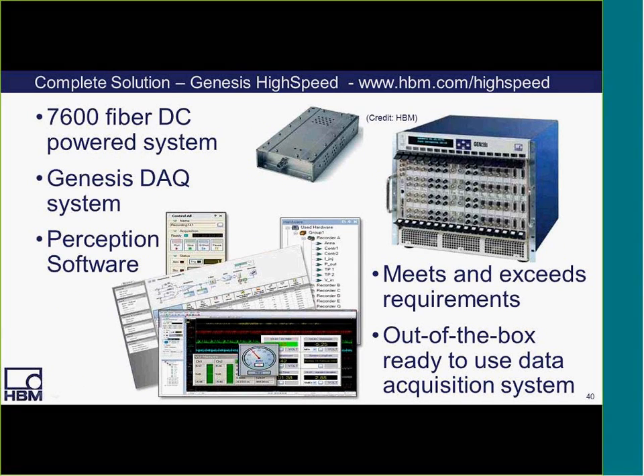So this resulted in a new ruggedized fiber optic isolated digitizer system, which is called the 7600, not only now used at NASA, but also at high power substations, and it's a perfect match for high powered ballistic applications as well. So this is the entire solution: the fiber optic isolated transmitter at the top middle, the Genesis data acquisition system shown at the right, and at the bottom middle you have the Perception software. So this met and exceeded the requirements right out of the box, ready to use, ready to run, and acquire data.